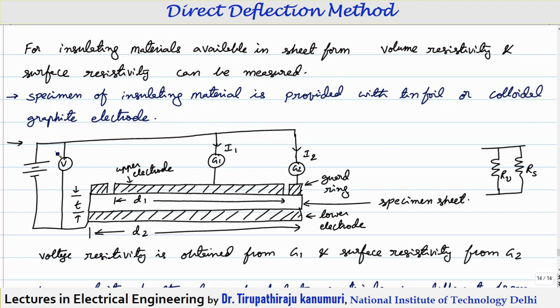Whenever you give the supply, two currents will pass. One current I1 comes through galvanometer 1, through the upper electrode, passes through the insulator and goes down — this current passes through the volume. The second path is through galvanometer 2, passing along the surface to the guard ring electrode and returning — this I2 is the leakage current through the surface. Under normal conditions without the guard ring, the resistance measured would be the parallel combination of volume resistance and surface resistance.